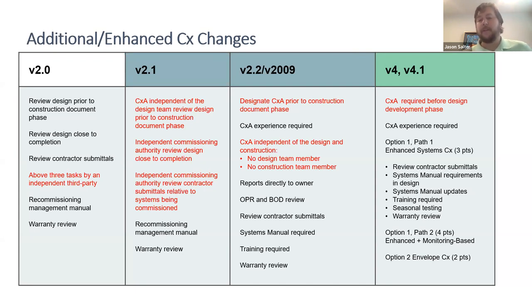Monitoring-based commissioning is sort of a more real-time version of measurement and verification from previous versions. But what it essentially boils down to is that you've included some sensors and meters on your energy use systems so that you can continuously monitor and ensure correct operation and performance of those systems as you move through the year or life of the building.